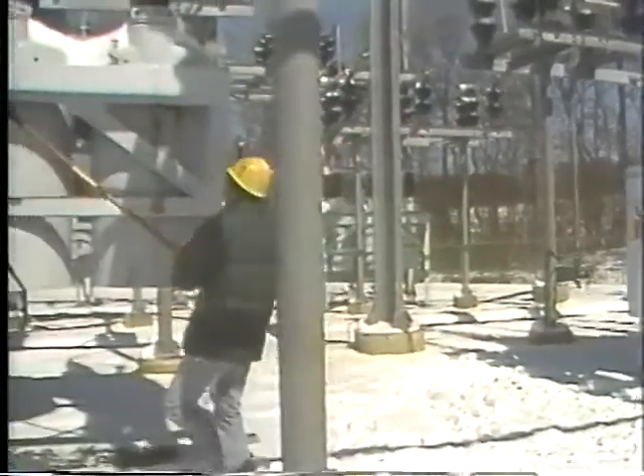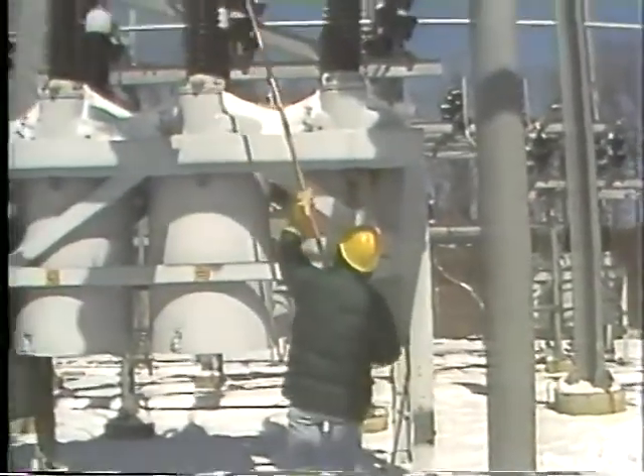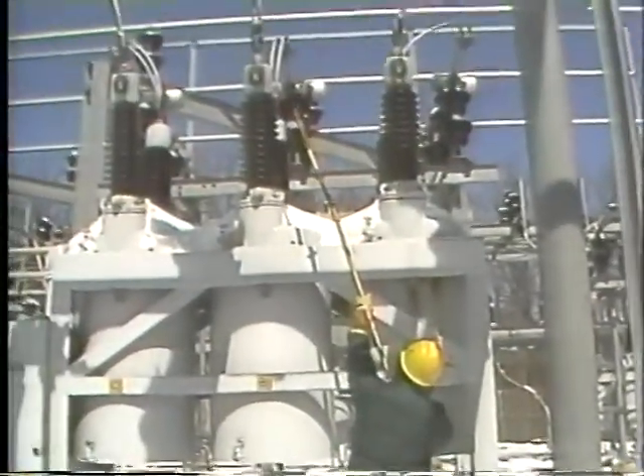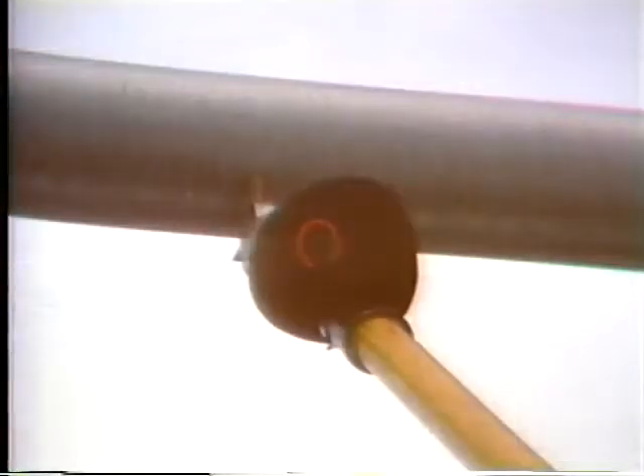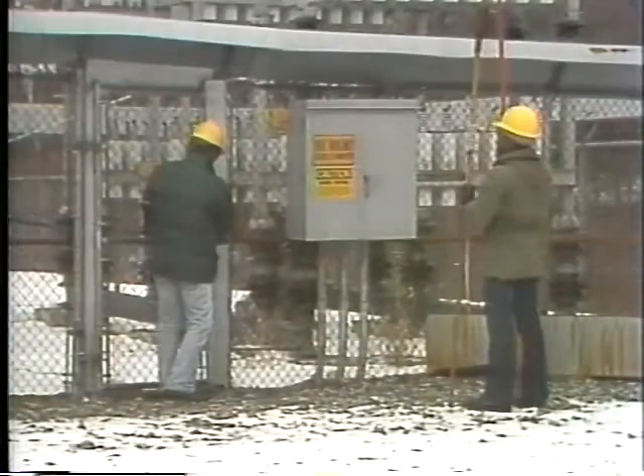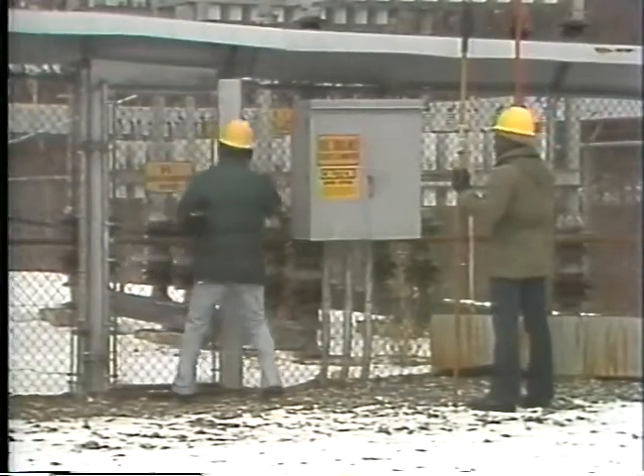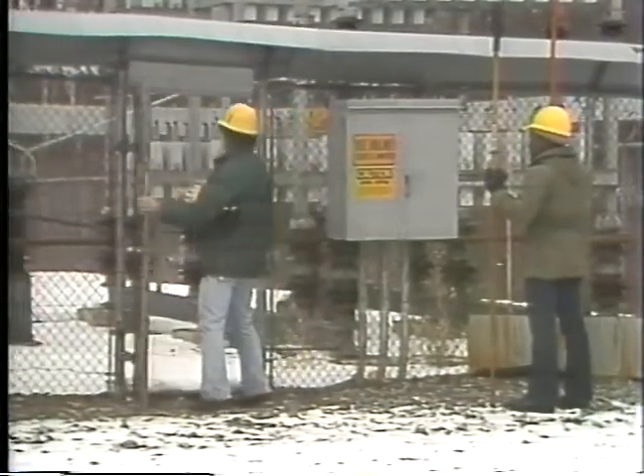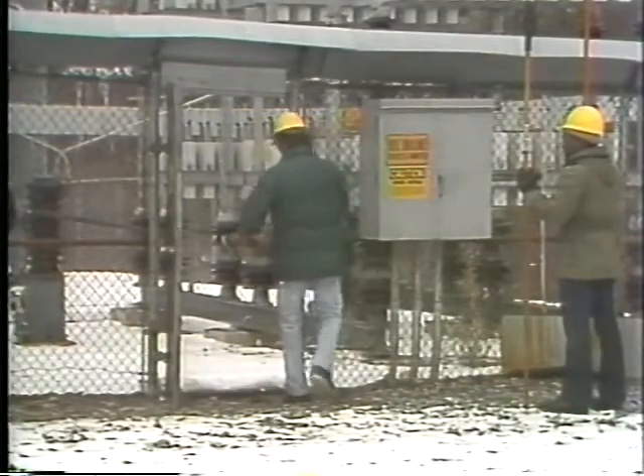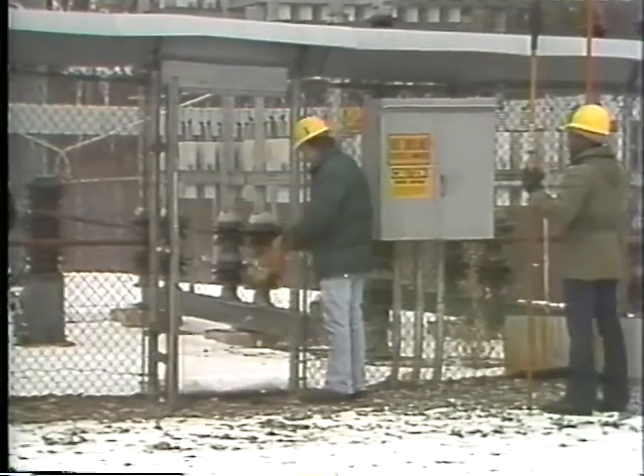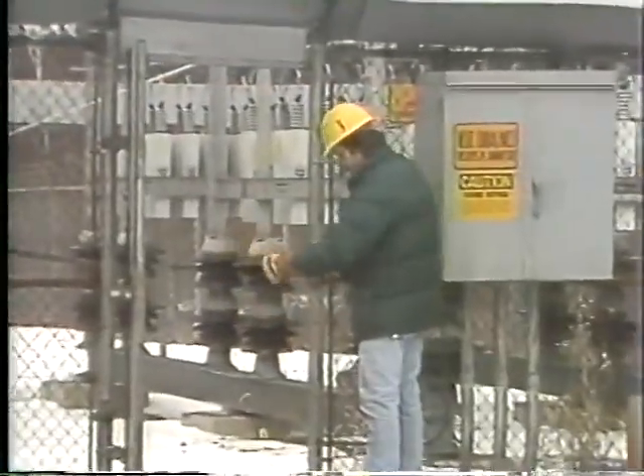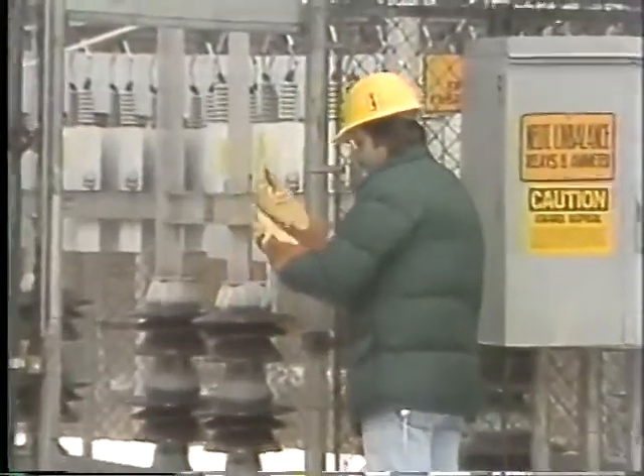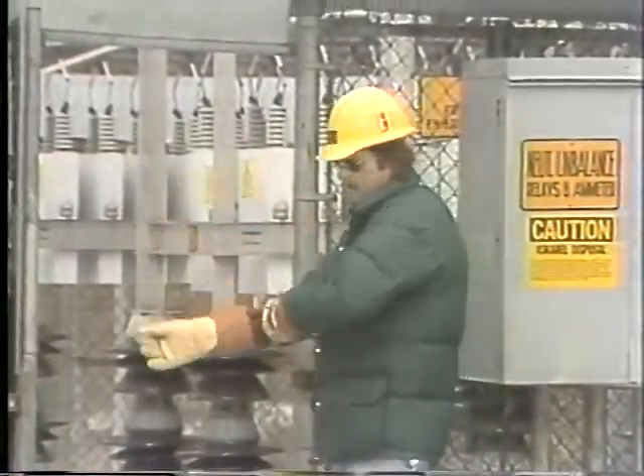During the wait, the electrician checks his voltage detector on an energized source. This type, called a glow tester, has a circular neon tube that glows when it comes near an alternating current source. Once the required 5-minute wait is over, he can open the gate leading to the capacitors. At this facility, a key interlock system controls access to the area. It can't be unlocked unless the capacitor bank disconnect switch is open.